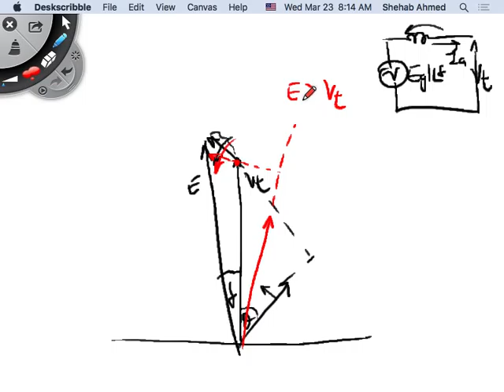The generator AVR, or automatic voltage regulator, is what controls the field current of the generator. This I field is controlled by a power electronics circuit, some MOSFET or rectifier circuit or whatever, right? So you have to produce a DC current. If you have an AC source, you have to create an AC to DC converter, and this AC to DC converter will have to control the current flowing into the synchronous machine's winding.